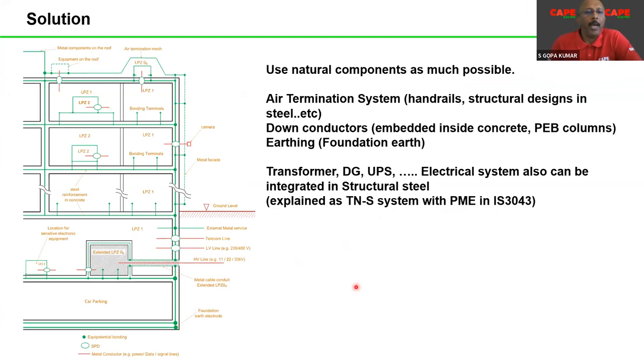Across India, we have designed, executed and tested probably more than 100 large multi-storied buildings and large industrial buildings with this technique, where there is no earth electrode in soil. Transformer neutral is connected, transformer body is connected, DG is connected, UPS is connected, lift is connected, your electronic installations are connected, BMS is connected, everything integrated into the natural material. And that is the best and recommended method, which is included in the IEC standards.